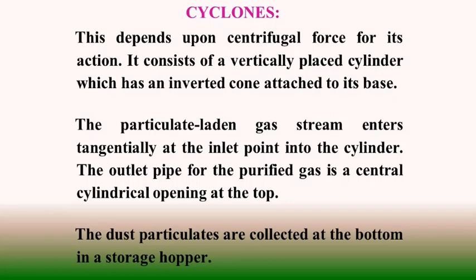Cyclones employ centrifugal force for the separating action. They consist of a vertically placed cylinder with a conical base. When the particulate-laden gas stream enters tangentially from the top of the cyclone, it has a swirling motion across the cyclone space. Dust is separated at the bottom and clean gas comes out from the top through a central pipe. The collected dust goes to a storage hopper.